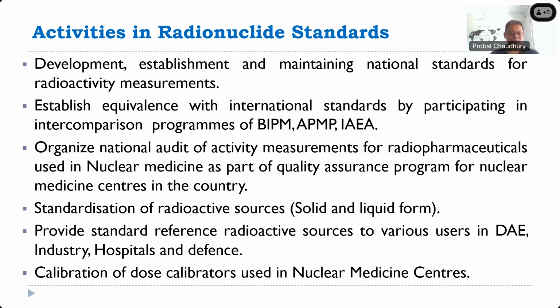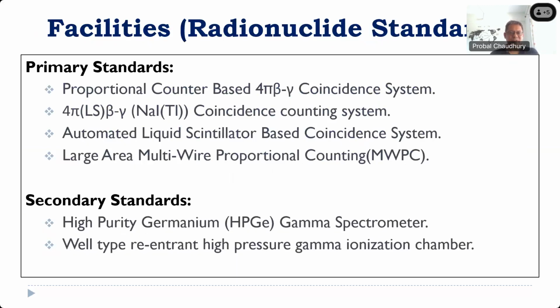Then the radionuclide standards group also carries out calibration of dose calibrators. In the nuclear medicine centers, they use radionuclide calibrators. Those calibrators have to be calibrated frequently, and we are providing the calibration traceability for the nuclear medicine centers. The facilities of radionuclide standards are a proportional counter-based 4-pi beta gamma coincidence system, then a 4-pi liquid scintillation based beta gamma with sodium iodide thallium activated coincidence counting system, then an automated liquid scintillation based coincidence system.